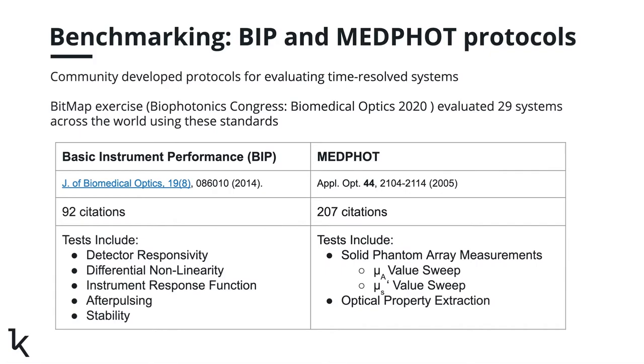To gauge the performance of our system we use well-established benchmarking protocols that have been used to evaluate TD-NIRS systems for several years. TD-NIRS systems have traditionally been bespoke, which made comparison between these difficult. The basic instrument performance or BIP protocol focuses on the raw system performance. The detector has traditionally been the focus of this protocol since most previous systems used large well-controlled picosecond lasers. We consider both our laser and detector performance as part of BIP. The second protocol we use is the MEDPHOT protocol. This evaluates the ability of a TD-NIRS system to accurately measure the optical properties of a diffusing medium, the ultimate goal we are after in doing TD-NIRS.